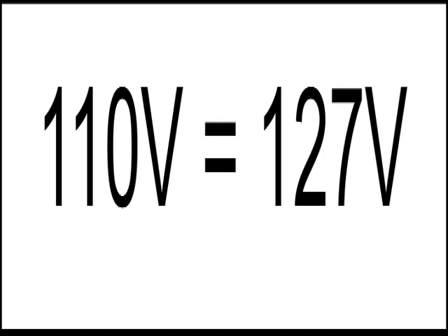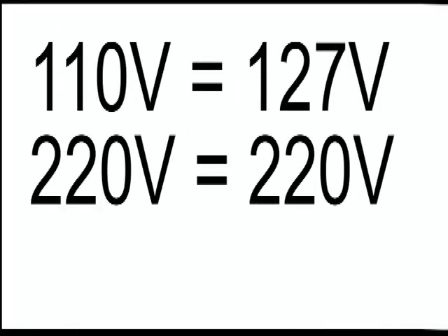That's why I said that with the battery analogy, there would be no absolute accuracy in terms of voltages. In other words, when an electrician is talking about 110 and 220 volts, he or she does it just for simplification. The actual voltage between each phase and the neutral is 127 volts, and the phase to phase voltage is 220 volts.